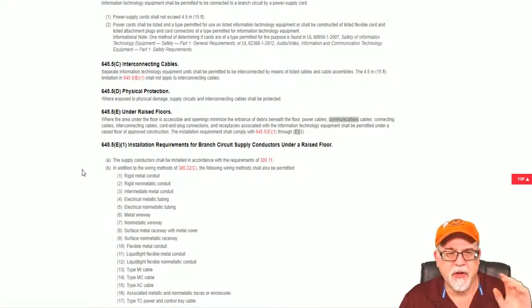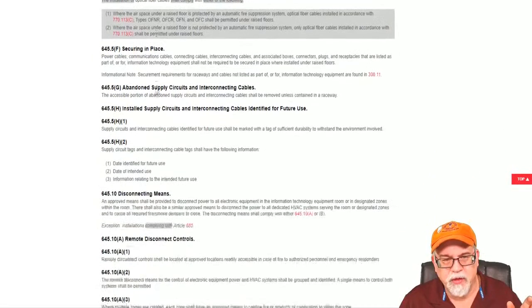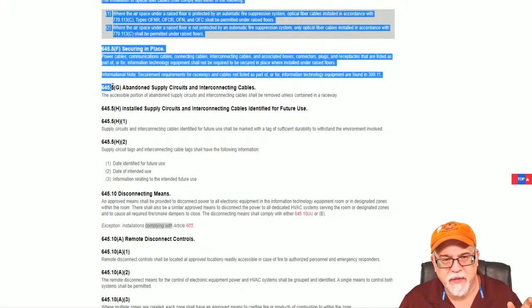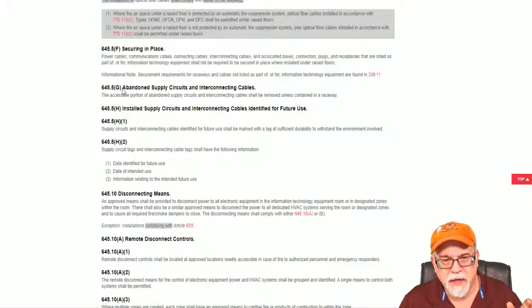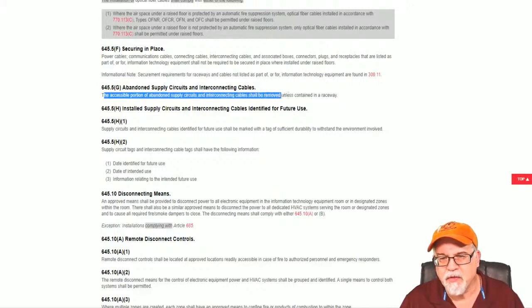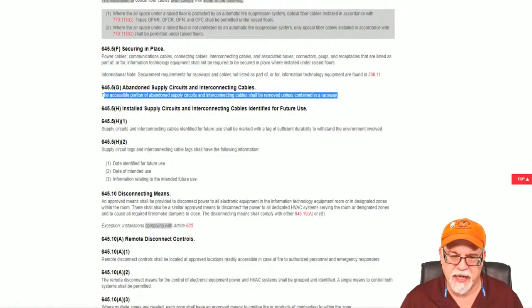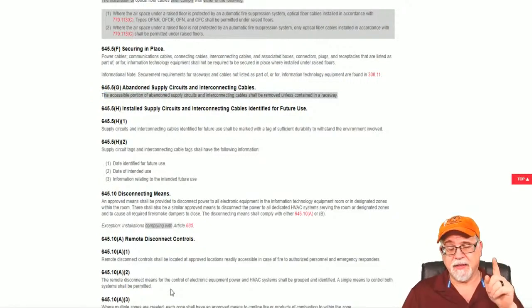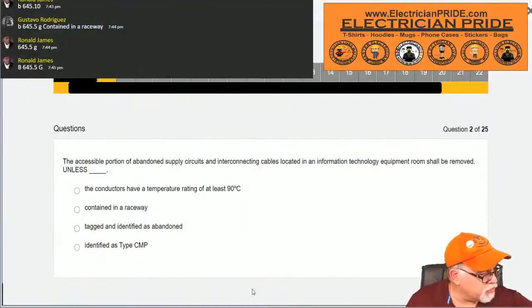Alright, so anyway, here we are, and what we're doing is going down and looking for bolds. Here's 645.5G, the abandoned supply circuits and interconnected cables, as everybody's putting in the comments, and it says the accessible portion of abandoned supply circuits and interconnecting cables shall be removed unless contained in a raceway. Aha, there's the answer. So we're going back to the browser material, and I'm going to say kudos to all of you that gave us that G.